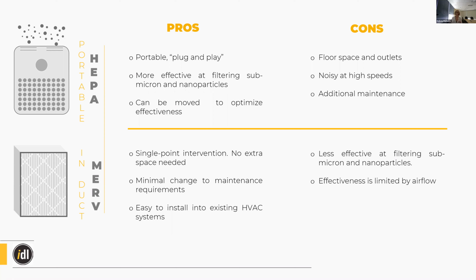So if you have a lobby with high occupancy, portable HEPA filters are really great to use in those high occupancy spaces. Also, wildfire smoke, which is something that we're starting to deal with more and more. If you can't bring in outdoor air, but there's obviously going to be some smoke getting into your house, the HEPA filters are going to be able to filter out the really, really fine smoke much better than the MERV filters will.